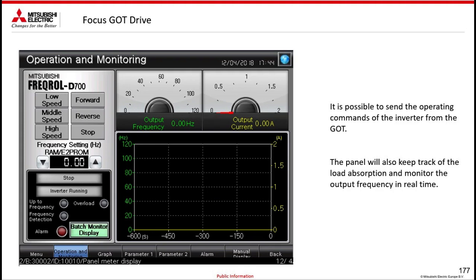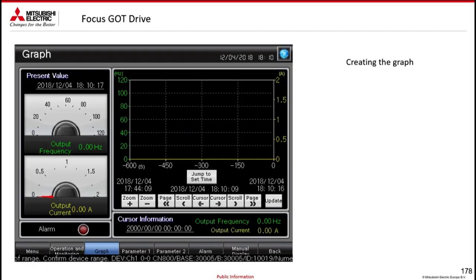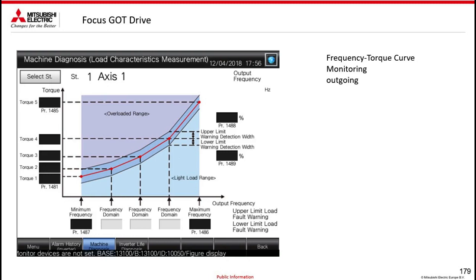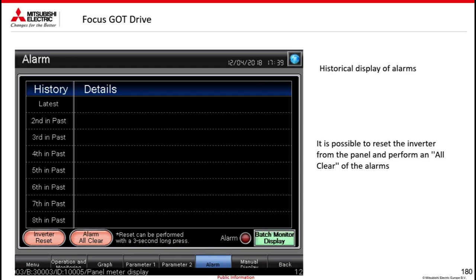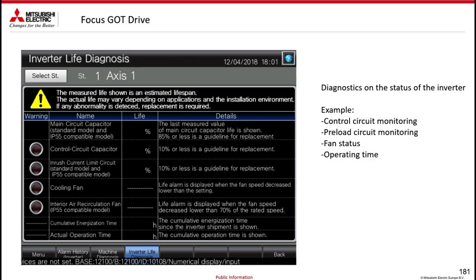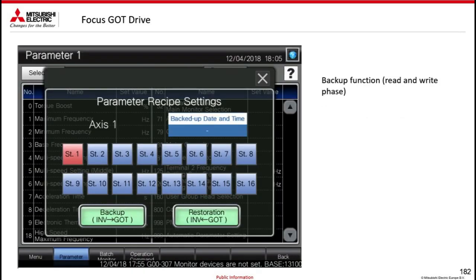For example, this is for an FR-D: giving a forward speed, stopping it, giving a frequency here in RAM, seeing the status, rather than making historical graphics. So you can also go with the cursor to see what happened over time. Going to see what I was already mentioning about the FR-F800, this diagnostic curve gives me the values, where I can go and play around a little bit if I want to make the reading a little more complicated. The alarm history with the possibility of resetting the inverter, and the history itself, the life of the inverter, the life of the capacitors, whether the fan works, and so on, all for 16 stations.